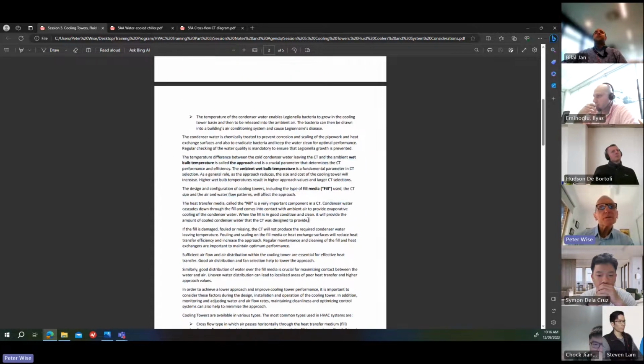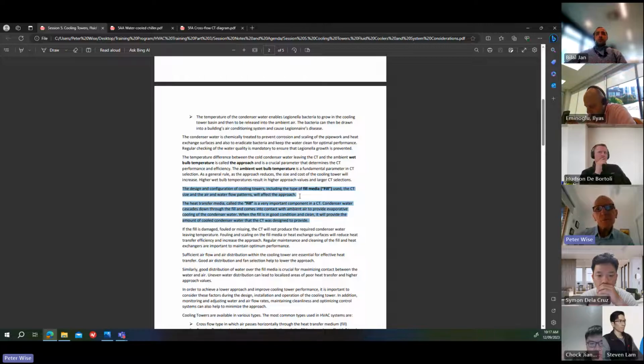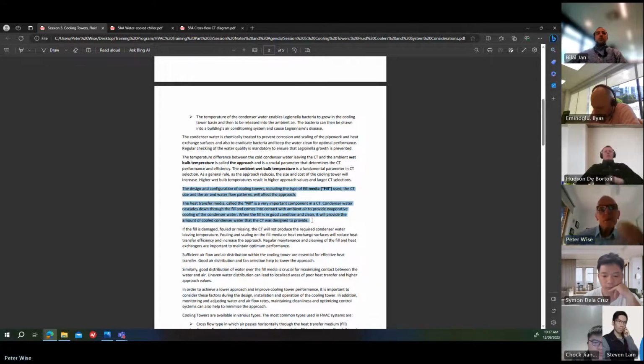Now, I just mentioned the fill in the cooling tower. The design and configuration of cooling towers, including the type of fill media, commonly called fill, used, the cooling tower size and the air and water flow patterns will affect the approach. There's a lot of parameters involved here. There's the approach, there's the water flow, there's the airflow. The motor size comes into it when you're looking at the airflow. So when you're selecting a cooling tower, all these factors need to be considered, but usually the suppliers will give you all this information. And these things can be changed. You can change water flows, you can change airflows, and it will affect the performance and the size of the cooling tower.